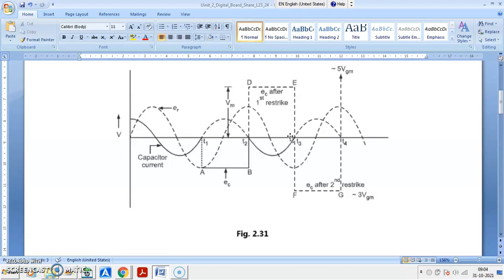The peak value of the initial transient voltage is twice that of the voltage. So normally you may have voltages of 4 times, 5 times, 6 times that occur across the contacts of the circuit breaker. And the energy, 1/2 CV square, across the capacitor is dissipated during the arc, which is very large, and this may cause damage to the circuit breaker.